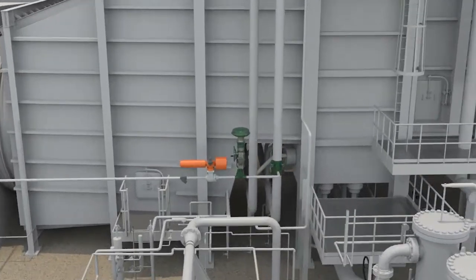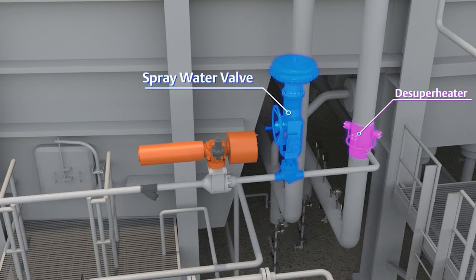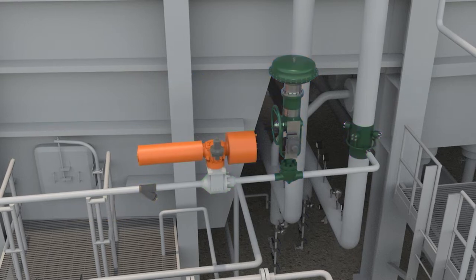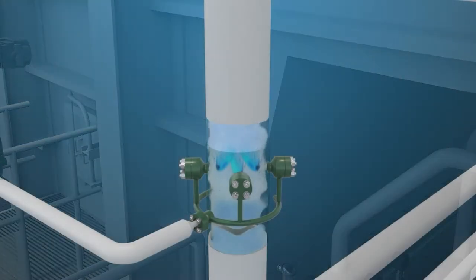Steam temperature is controlled using an attemperating system. It consists of a de-superheater, spray water valve, spray water block valve, and a strainer. The control system measures the temperature of the steam, compares it to set point, and then increases or decreases the spray water accordingly to maintain temperature set point.